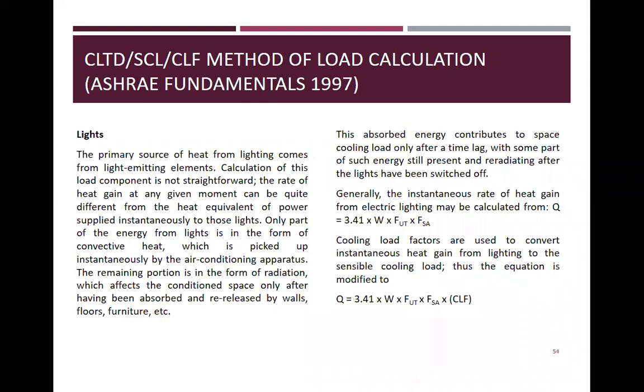Next is the lights. The primary source of heat from lighting comes from light-emitting elements. Calculation of this load component is not straightforward. The rate of heat gain at any given moment can be quite different from the heat equivalent of power supplied instantaneously to those lights. Only part of the energy from light is in the form of convective heat, which is picked up instantaneously by the air conditioning apparatus. The remaining portion is in the form of radiation, which affects the conditioned space only after having been absorbed and re-released by walls, floors, or furniture, etc. This absorbed energy contributes to space cooling load only after a time lag, with some part of such energy still present and radiating after the lights have been switched off.